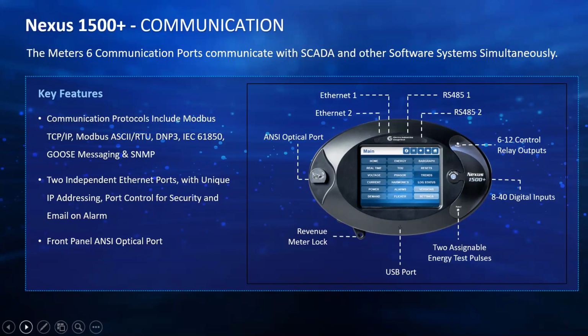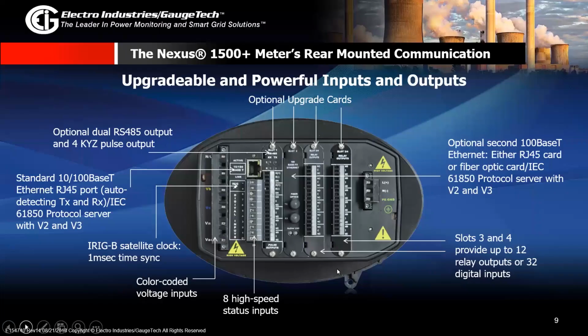This is just showing what the back of the meter looks like. If you can see here, there are 4 card slots at the back, and you can actually pick and choose what kind of option cards you want to put into the meter. So there are 4 different slots. You can choose what communication options you want. And down the line, if you want to change or upgrade or add some communication capability to your meter, it's a very simple field upgrade. You don't have to actually swap out the entire meter and put in a new meter.